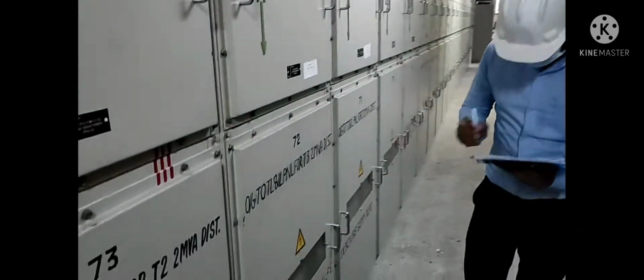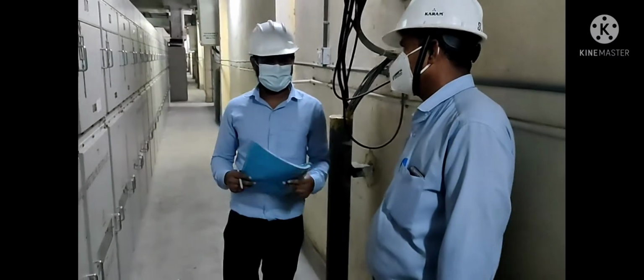Before opening the power cable chamber, our supervisor cross-checks it with our internal permit. First we open the power cable chamber. Now we ensure there is no charge available with the help of the live line detector. For that, first we check the live line detector by pressing its switch and cross-check it with the live current. To proceed to the next step, we provide earthing to our earthing rod, and after that we touch the earthing rod one by one to all the phases.